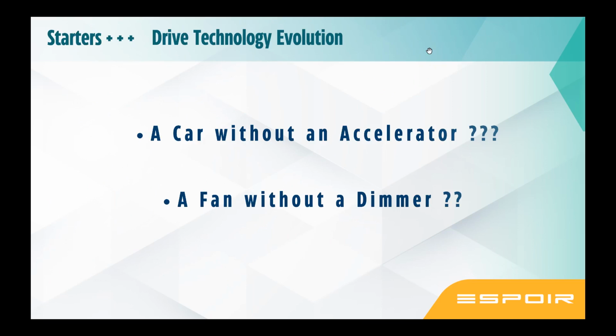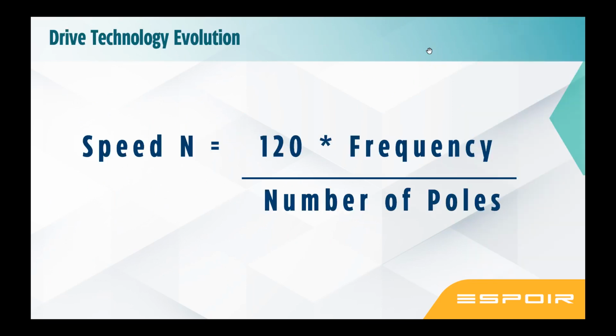But whenever you reduce the speed on the secondary side, on the primary side you lose energy. So what if you have a system which controls the speed and at the same time doesn't lose energy, which can be an energy efficient system? So that's when the VFD came into the picture.